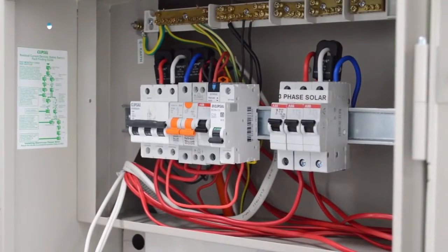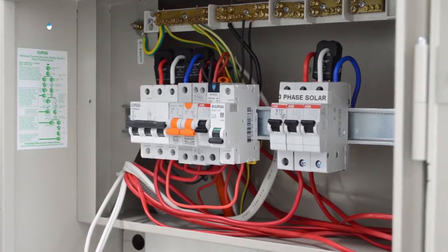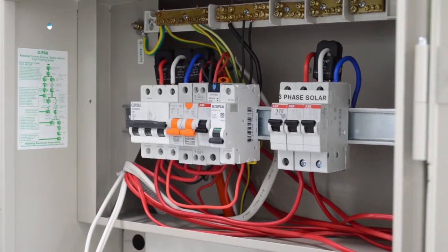It's important when switching to first assess the switchboard for some suitable circuits that can be switched. The relays of the CT200 users are normally open 20 amp rated relays. Circuits must be 20 amp or less in order to be switched. There is a maximum of 3 relays per unit, which means 3 circuits that can be switched per unit.